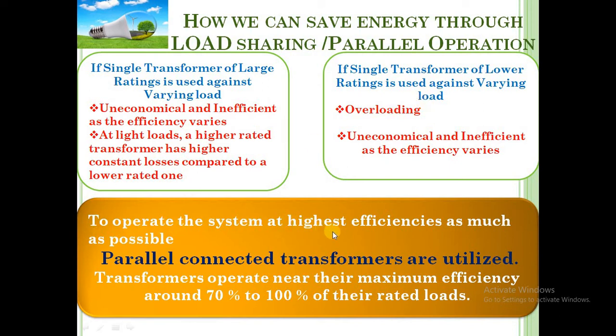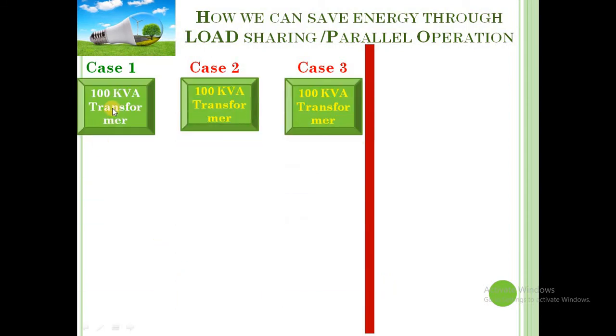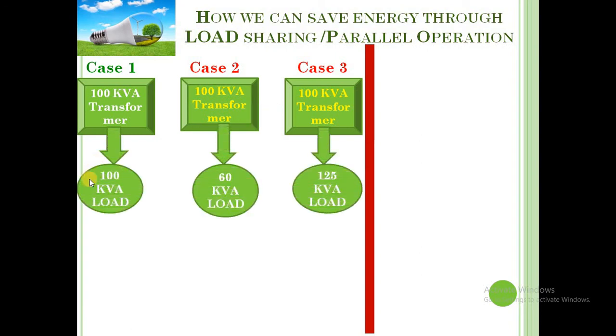Hence, to operate the system at the highest efficiency, we must do a parallel connection of transformers, because a transformer operates near its maximum efficiency at around 70% to 100% of its rated load. Now we'll see how overloading and underloading will happen if a single transformer is used, and how we can save energy if two or more transformers are connected in parallel. So in the first case, a single 100 kVA transformer is taken in these three cases. Now the load is varying.